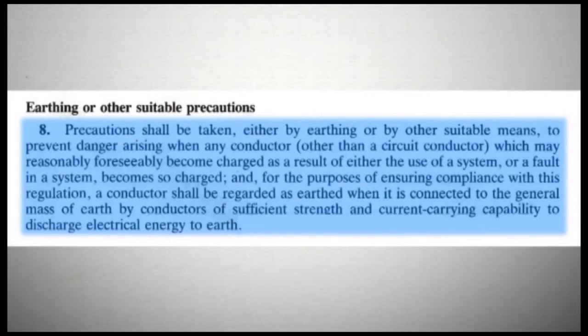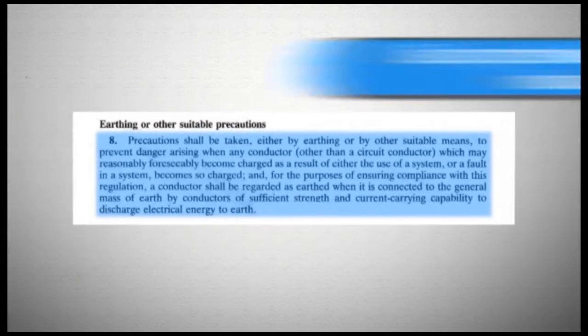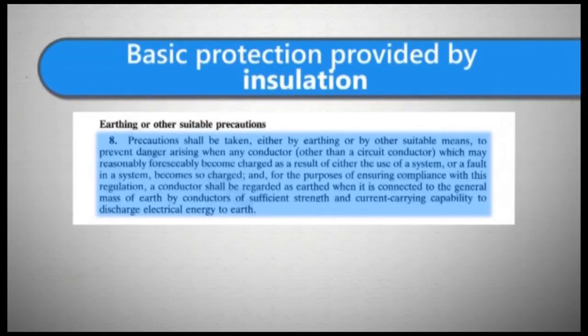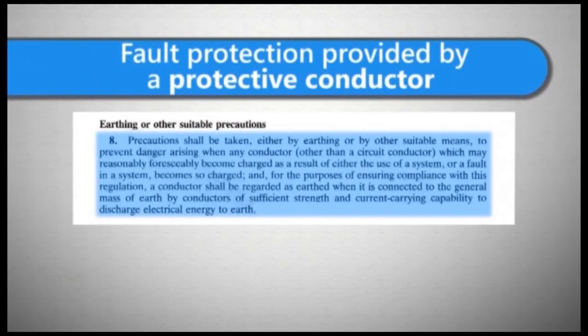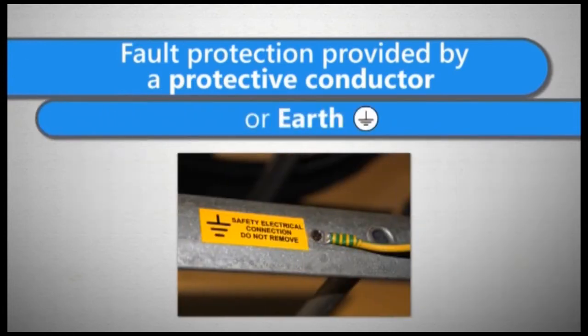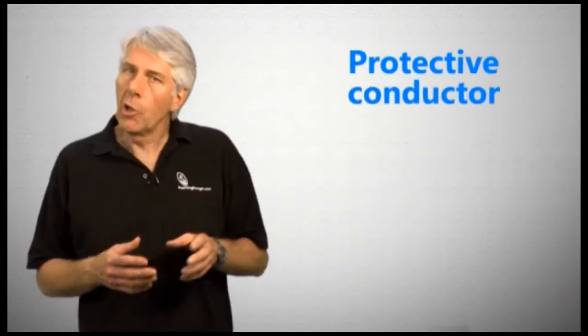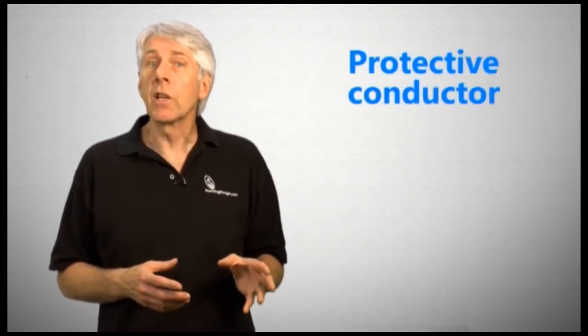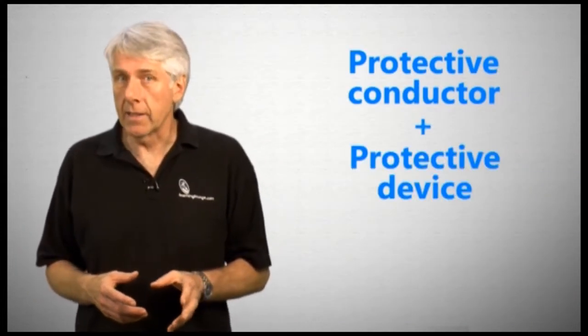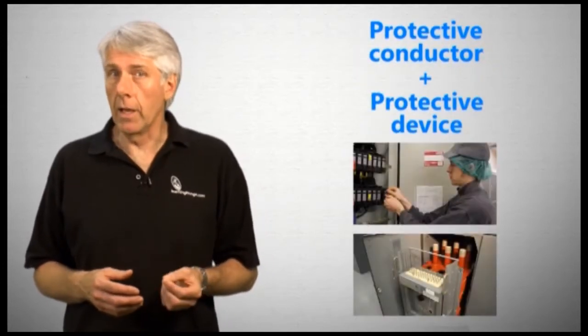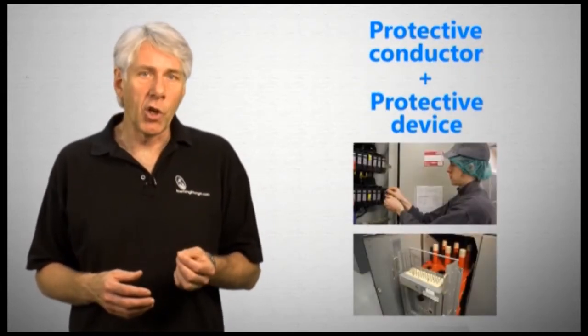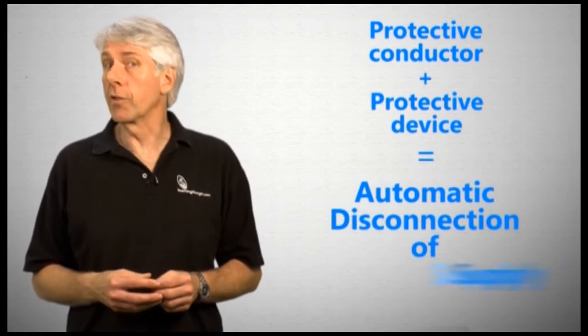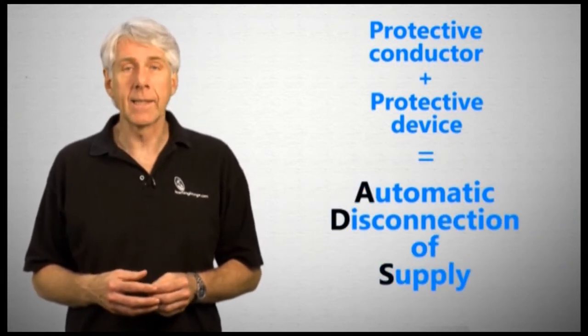There are a number of ways of satisfying Regulation 8. Probably the most common is by having basic protection provided by insulation and fault protection provided by a protective conductor or earth attached to any exposed metalwork. The protective conductor is used in conjunction with a protective device, such as a fuse or circuit breaker, to form a protective measure known as automatic disconnection of supply, or ADS.